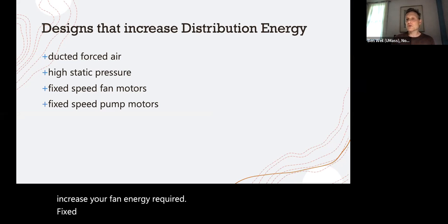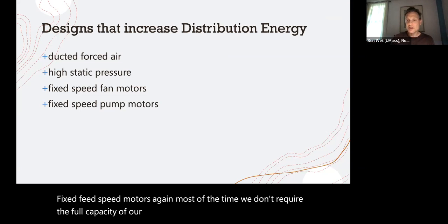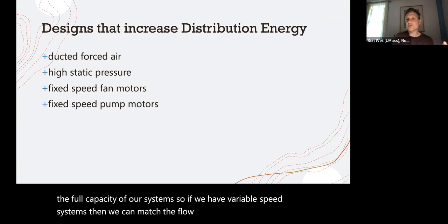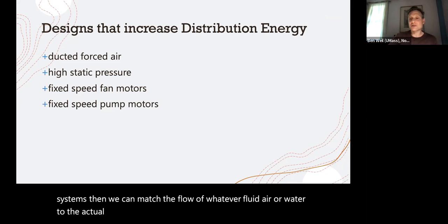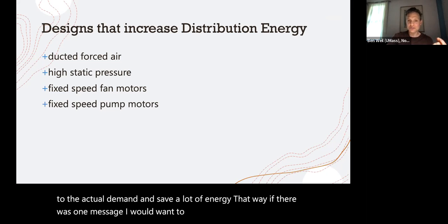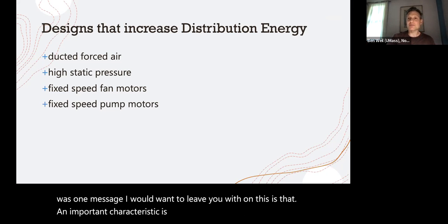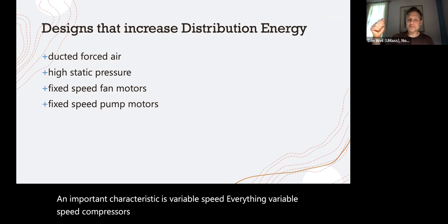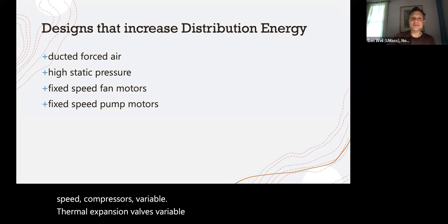Fixed speed motors. Again, most of the time we don't require the full capacity of our systems. So if we have variable speed systems, then we can match the flow of whatever fluid, air or water, to the actual demand and save a lot of energy that way. If there was one message I would want to leave you with on this, it is that an important characteristic is variable speed everything. Variable speed compressors, variable thermal expansion valves, variable pumps, variable speed fans.